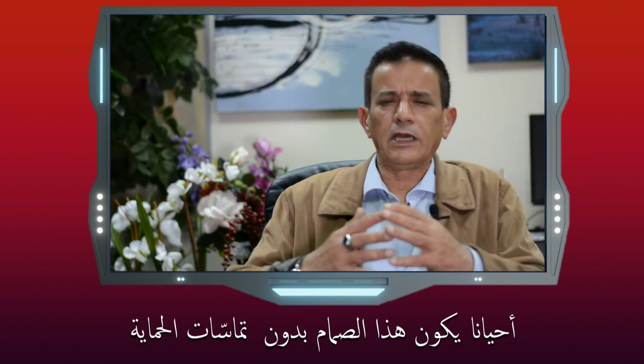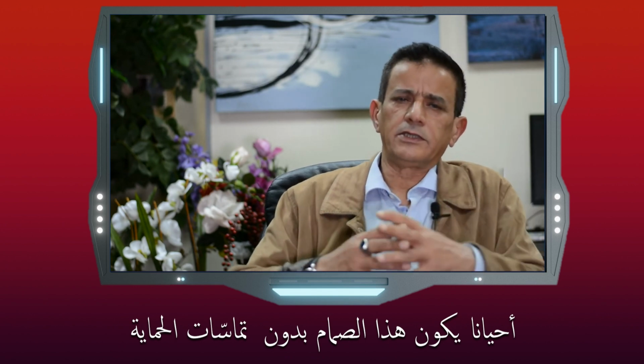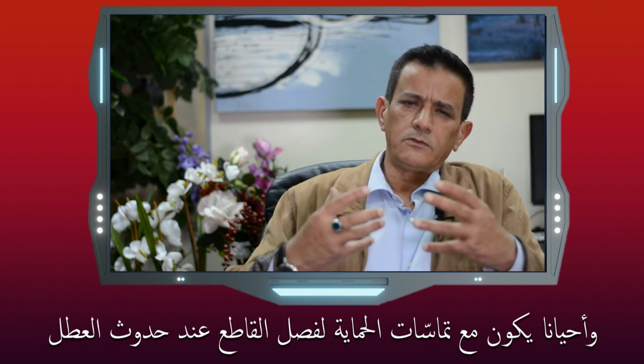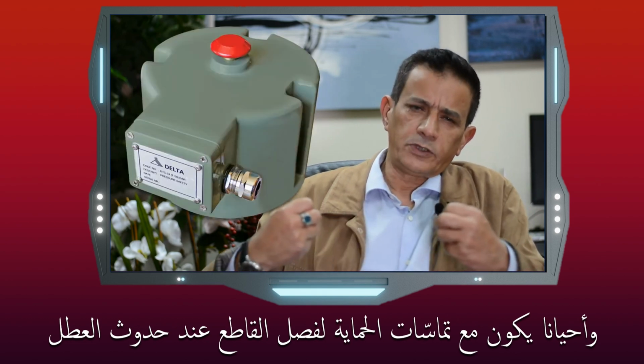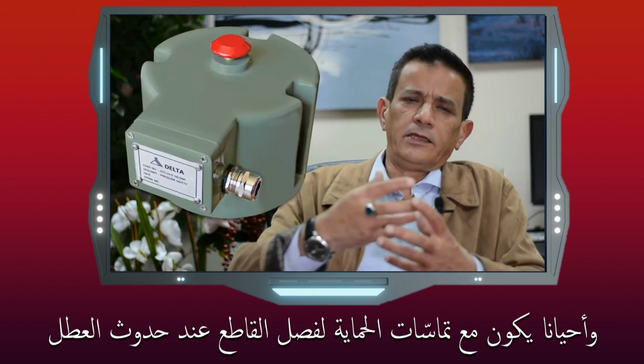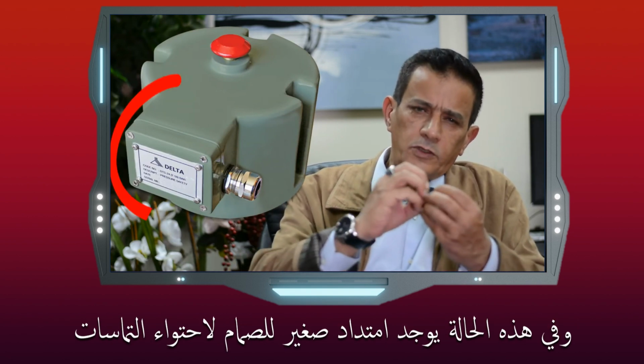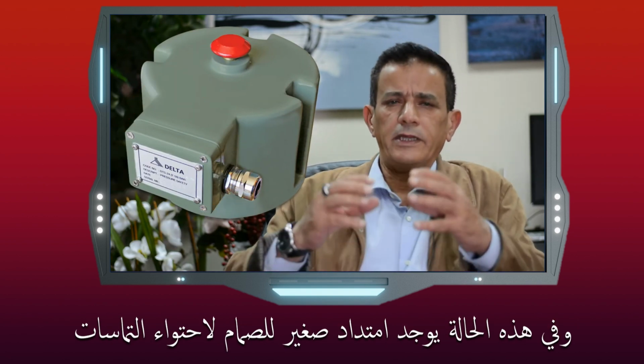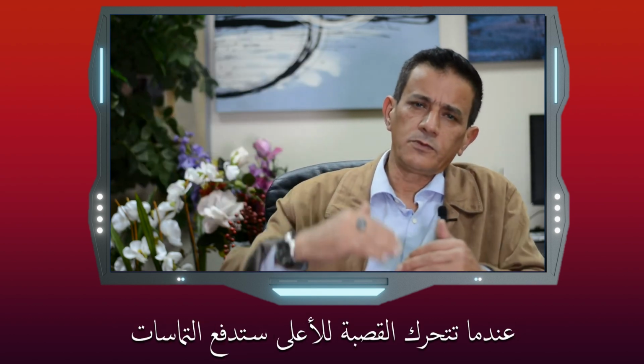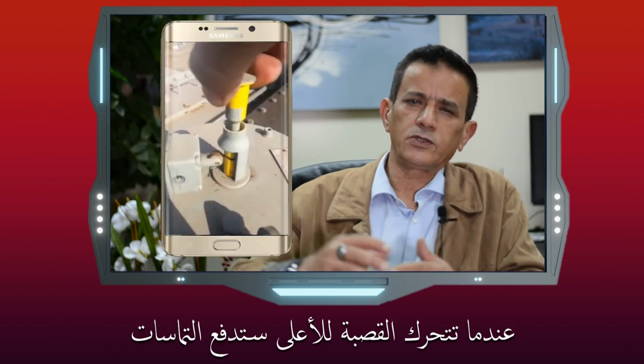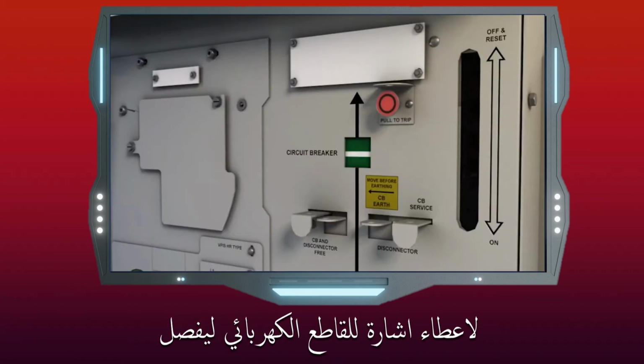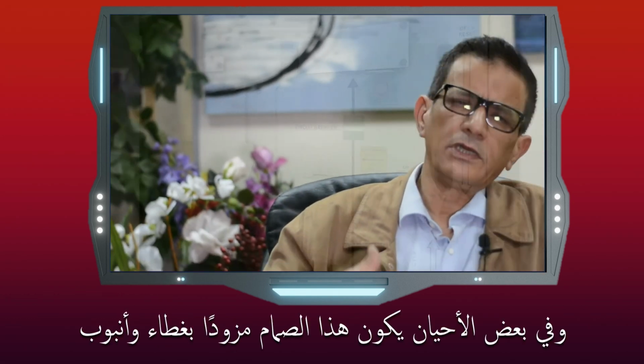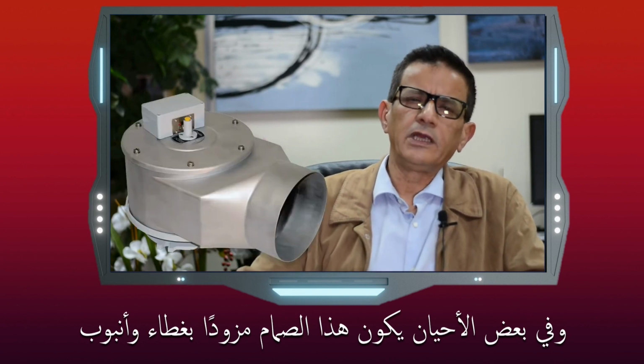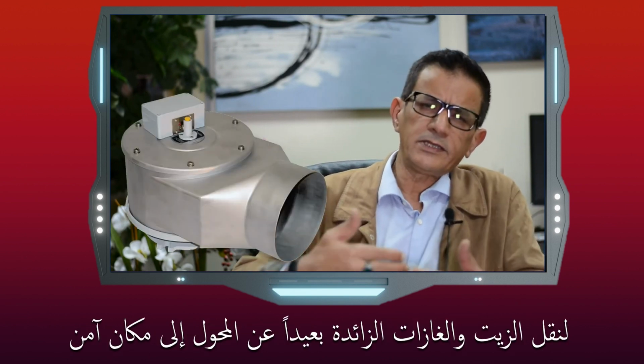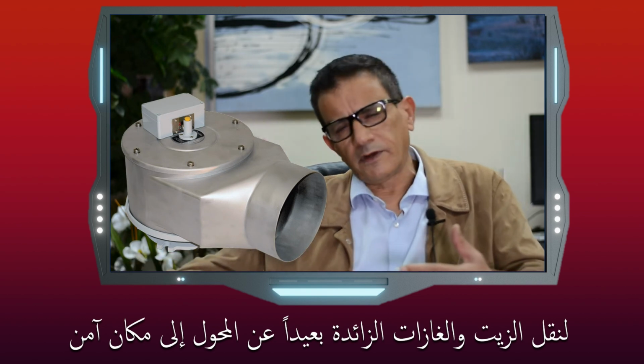Normally this PRV has a special design made of brass or aluminium, and sometimes painted aluminium, because this PRV is supposed to withstand tough conditions, very high temperatures. And whenever this is pulled up, there will be a way for the gases to go out from the PRV. Sometimes this PRV can come like this without contacts. Sometimes it comes with contacts to provide protection to trip the circuit breaker, and in that type you will find a small extension of the PRV where the contacts are enclosed. When the rod is moving upwards, it will push the contacts to give a signal to the circuit breaker to trip. And sometimes this pressure relief valve is equipped with a tube or cover to lead this extra gas and oil away from the transformer to a safe place.